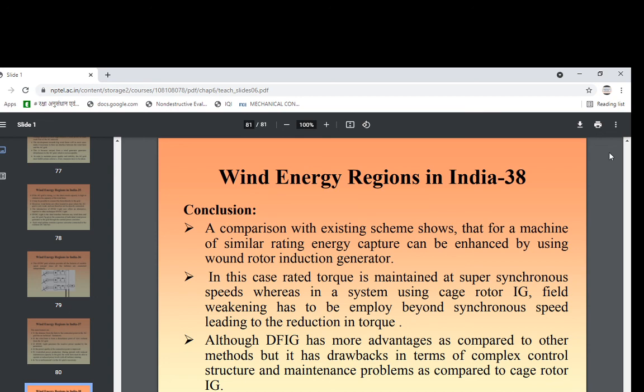Now, coming to the conclusion of today's video: a comparison with the existing scheme shows that for a machine of similar rating, energy capture can be enhanced by using a wound rotor induction generator. Next point, in this case rated torque is maintained at supersynchronous speed, whereas in a system using a cage rotor IG, field weakening has to be employed beyond synchronous speed, leading to a reduction in torque. Although DFIG has more advantages as compared to other methods, it has drawbacks in terms of complex control structure and maintenance problems as compared to the cage rotor. The use of an HVDC link for large wind farms is the best choice in terms of great interaction and long distance. Okay, thank you.